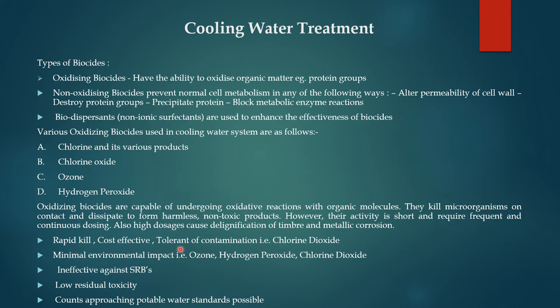Chlorine is rapid-kill, cost-effective, and tolerant of concentration variations. Minimal environmental impact is associated with ozone, hydrogen peroxide, and chlorine dioxide. Chlorine dioxide is ineffective against sulfur-reducing bacteria but has low residual toxicity, with counts approaching potable water standards. These are characteristics of oxidizing biocides.